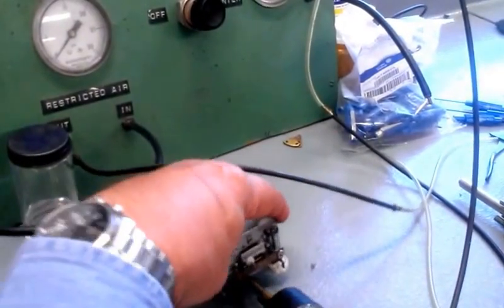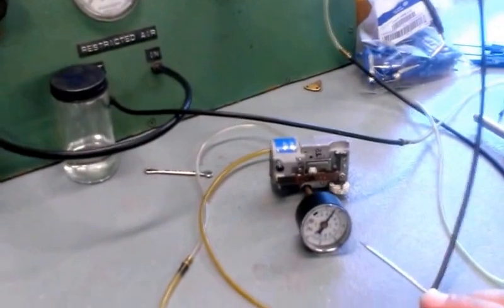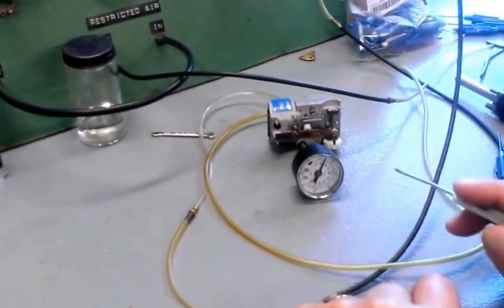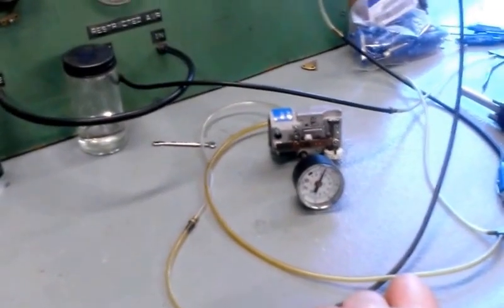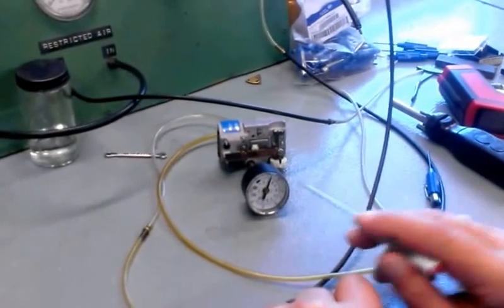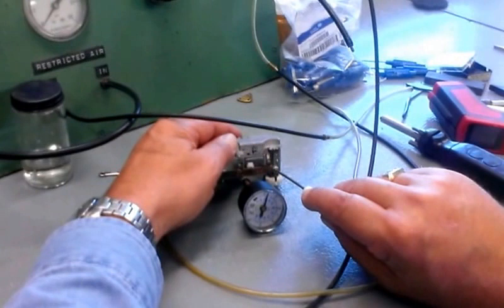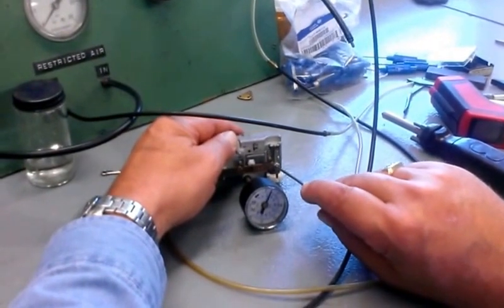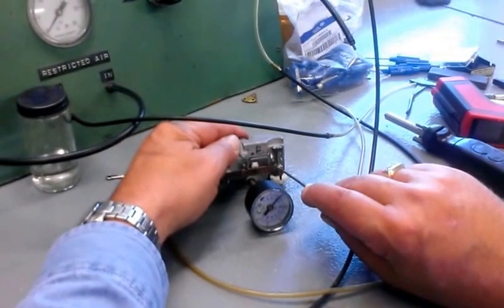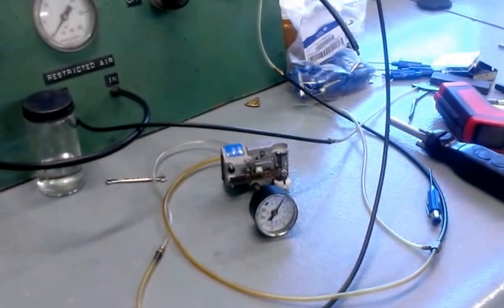Also, though, if I set this down, you'll probably see that that pressure is going to start to fall, because with my hand out of the picture, the thermostat is gradually starting to cool to room temperature. So, what I'm saying is you should check it. I'm at 7 pounds now. I need to go up a little bit. Unfortunately, you do have to handle these somewhat. But there, I've recalibrated it. I think we're good there.